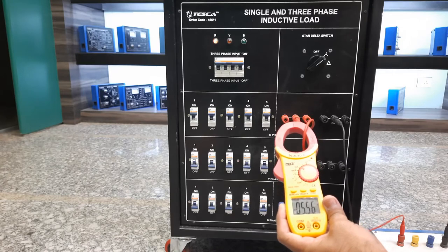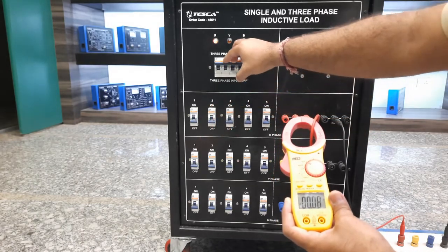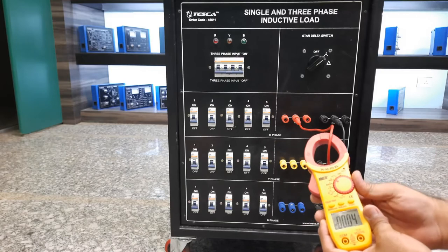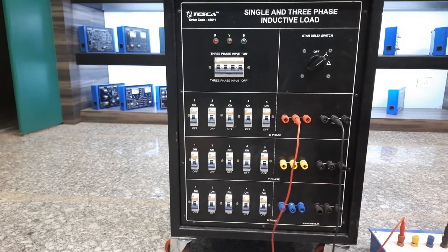So here you can see with single phase on R and neutral, we can load up to 0.556 amperes in single phase condition. After testing, turn off all the MCBs and the main MCB and power source. Now for extending to 15 steps, or 10 steps as well, we just need to connect all three phases in series.